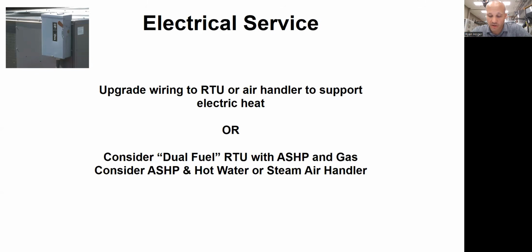If you have a gas-fired rooftop unit, this becomes more of a challenge because with a gas-fired packaged rooftop unit, you don't get a lot of choices on things. And I don't think anyone makes a gas-fired rooftop unit that also has a heat pump in it. For a while, we had one supplier that was doing it for 3, 4, and 5 tons only, but nothing bigger. And maybe there are still guys that do it like that. But if you have a rooftop unit, you don't have a lot of options here. If it's a split system, it's super easy. It's almost a no-brainer to do a dual fuel system when you have a split system with a hot water boiler or steam boiler.